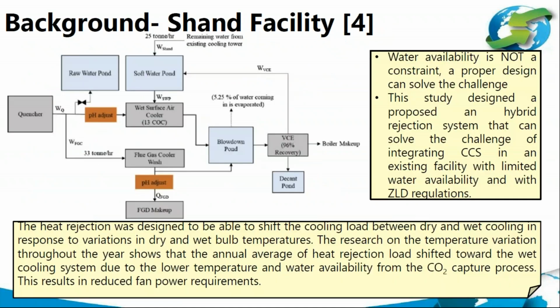This is a graph from their study. I wanted to mention that the heat rejection system was designed to be able to shift the cooling load between dry and wet cooling in response to variations in dry and wet bulb temperatures.